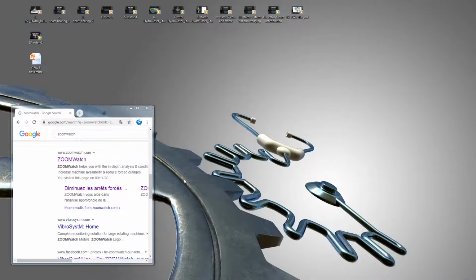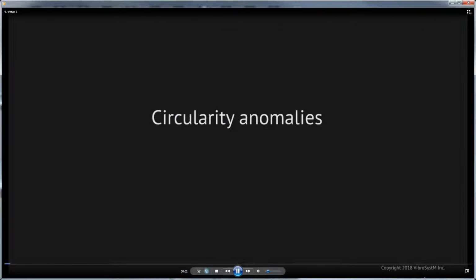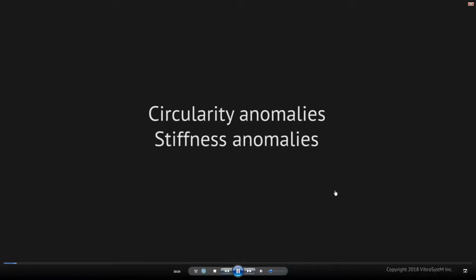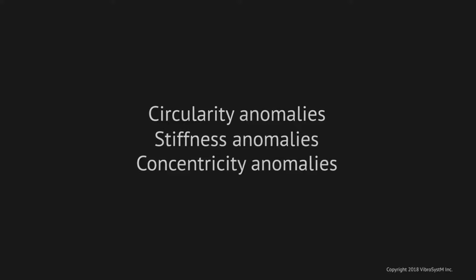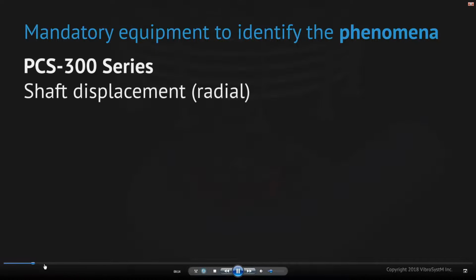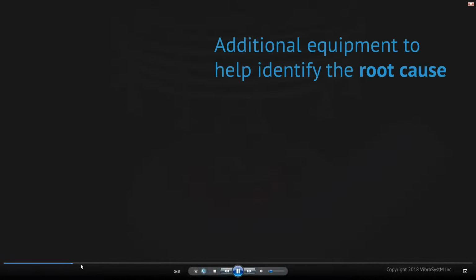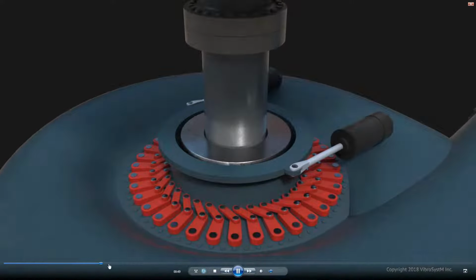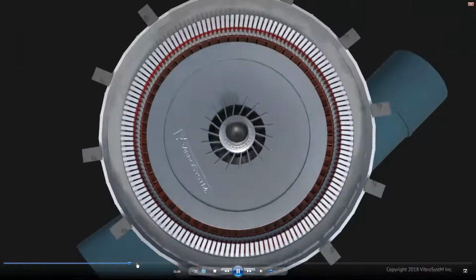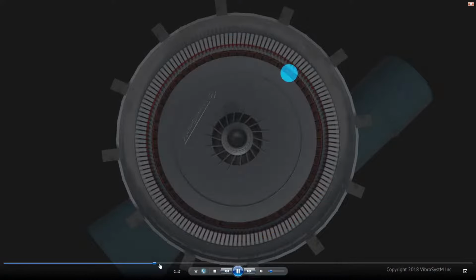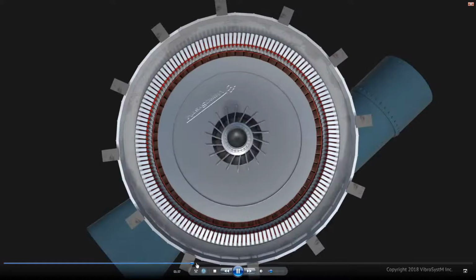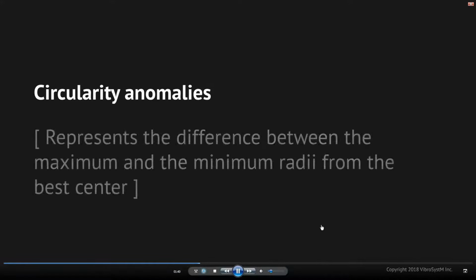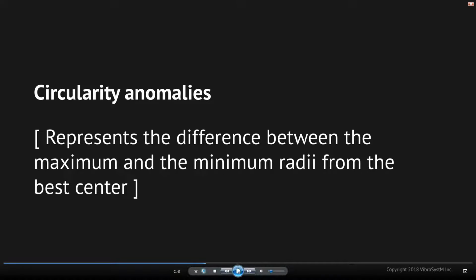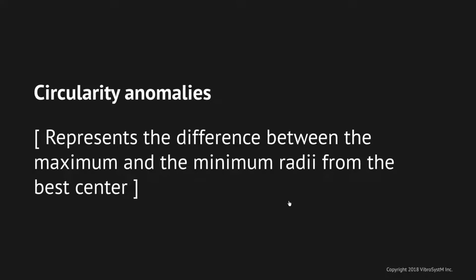Okay, so that was the video on the rotor, and I want to show you the same concept with the stator. Again, things that we look at from the perspective of a stator. Again, circularity, stiffness, concentricity, but from the perspective of the stator. The equipment that is required, we can skip that because it's basically the same equipment that we use to look at the rotor, but now we're looking at the stator. Okay, so all the same equipment. So, circularity anomalies from the perspective of the stator. Well, it represents, again, the difference between the maximum and the minimum radii from the best center.